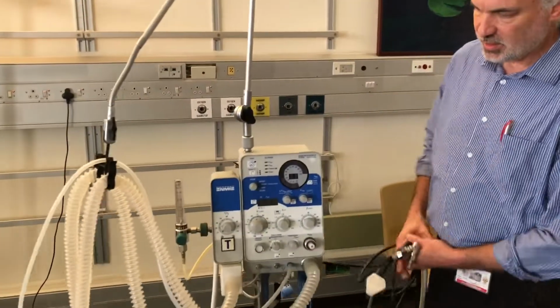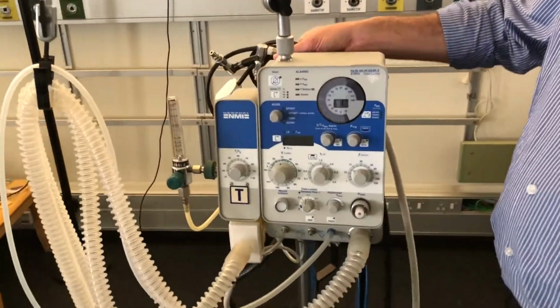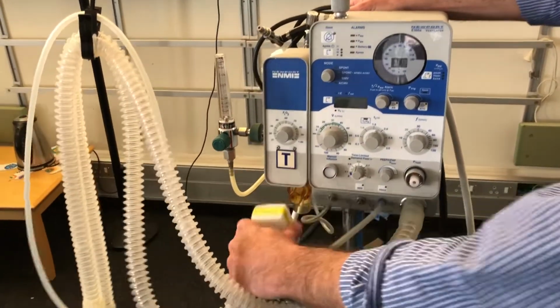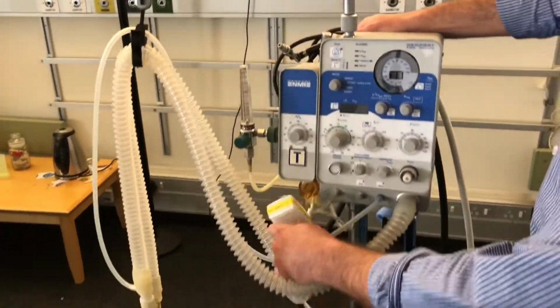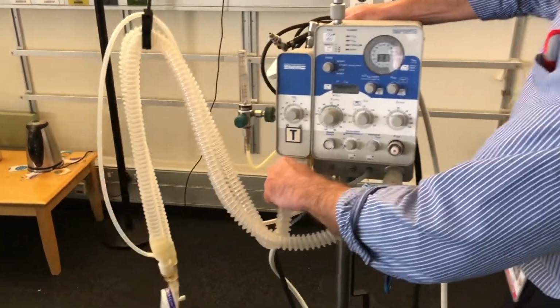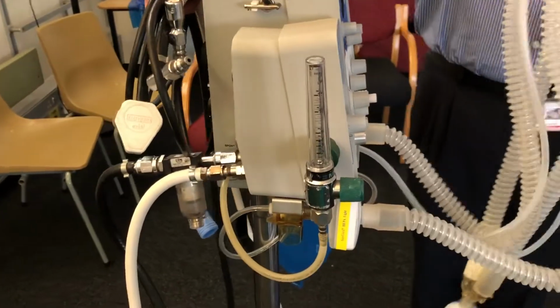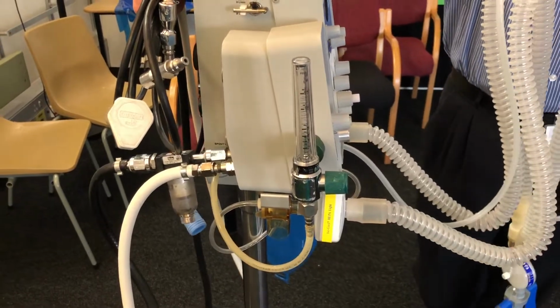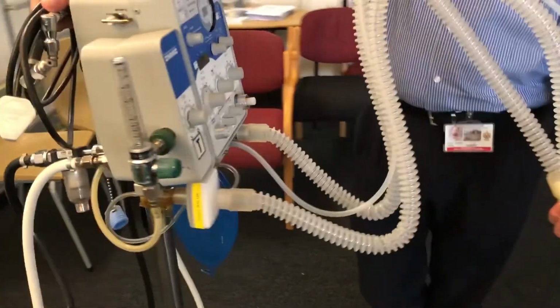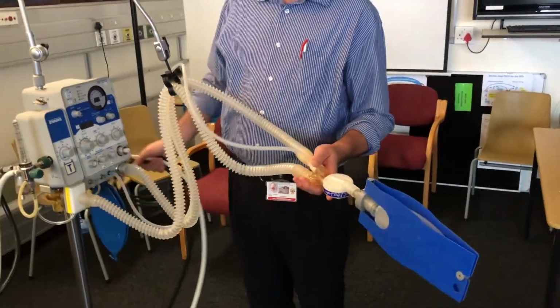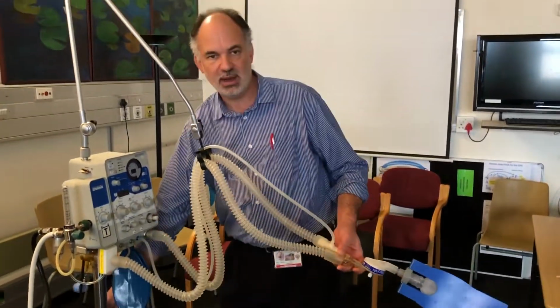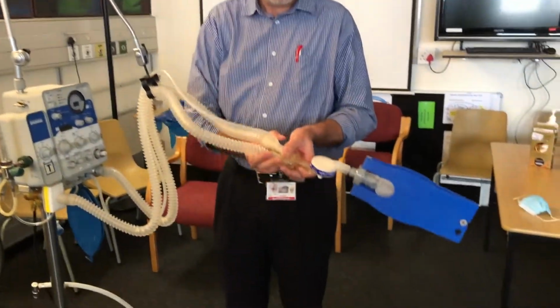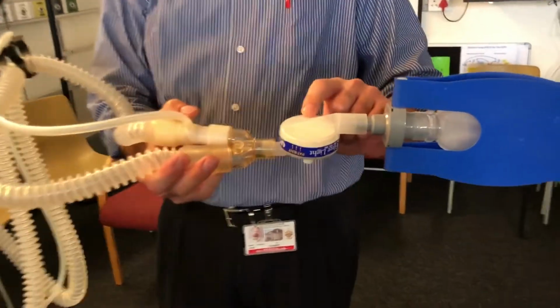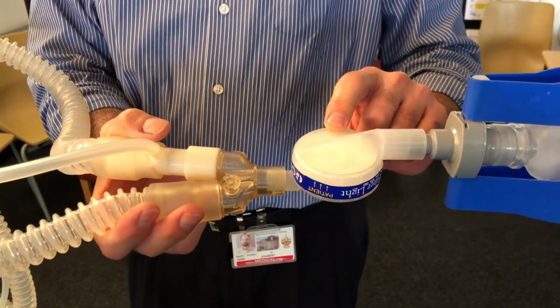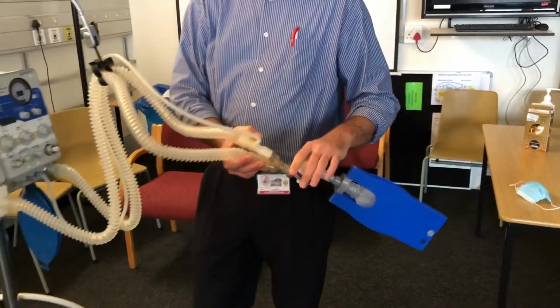If we come around to the front of the machine, then just to point out that we've got a bacterial filter on the expiratory limb of the circuit. Please make sure it's always there. And we've got a rotameter on the side of the machine, which I'll go through the detail of a little more in a few moments' time. And then last of all, because this ventilator doesn't have a humidifier on it, if you are ventilating a patient with this ventilator, then please make sure there's a heat moisture exchanger in the circuit before you connect it to the patient.